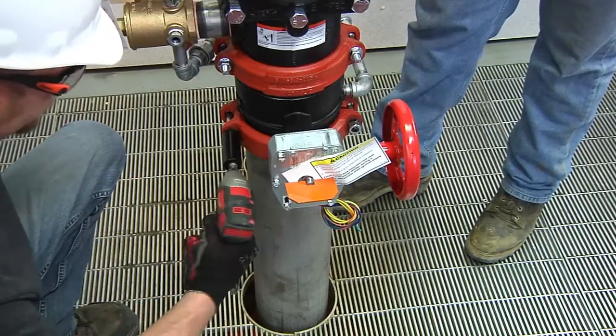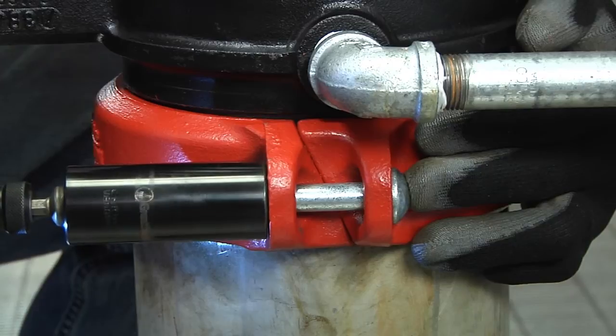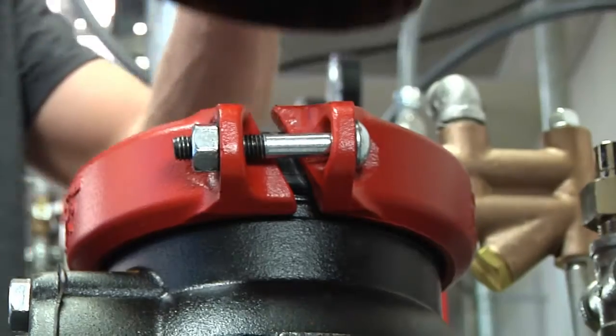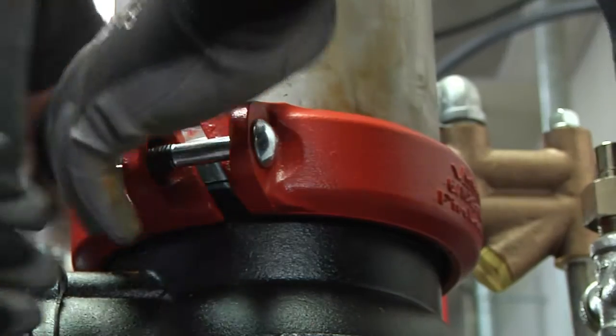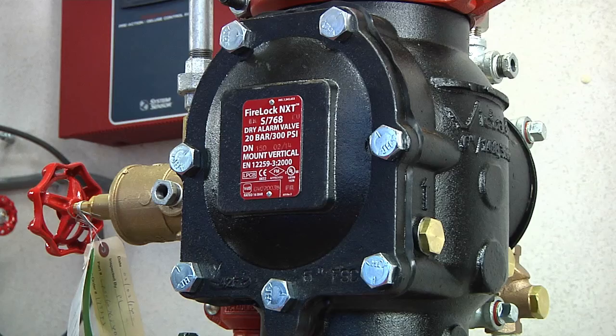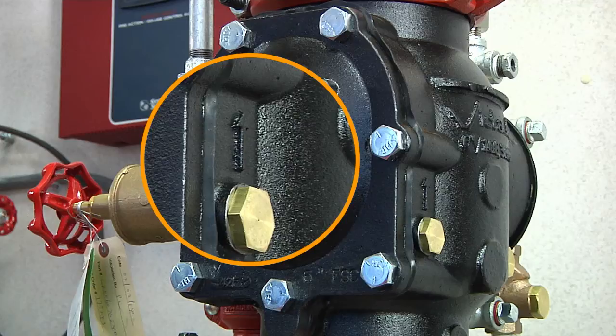Tighten down the FireLock EZ Style 009N by alternating evenly on each side until pad-to-pad contact occurs. Push a Style 009N rigid coupling into the top of the valve, then insert the pipe and correctly tighten the coupling. FireLock NXT Series 768 dry valves should only be installed in the vertical position with the arrow on the body pointing upwards.